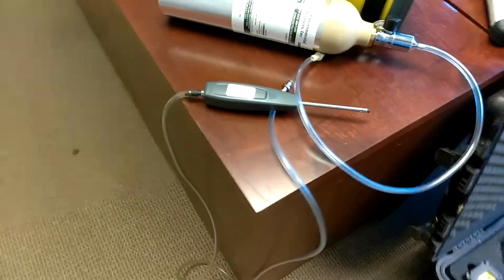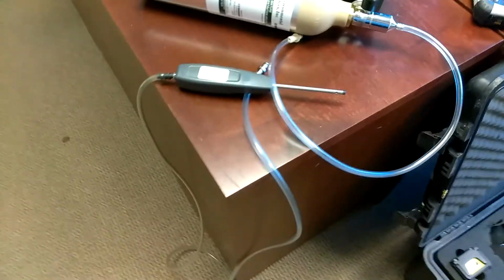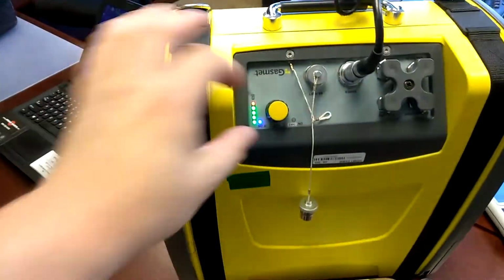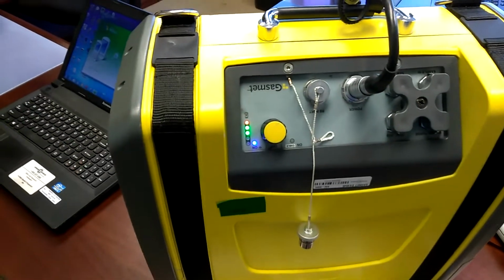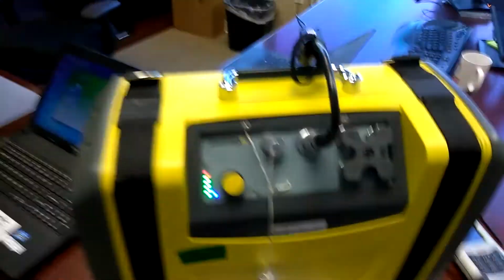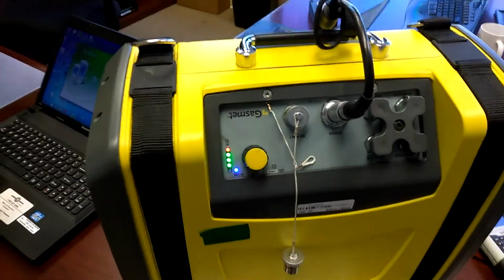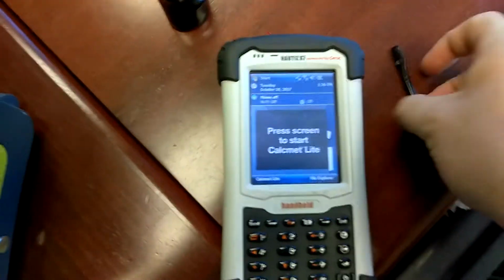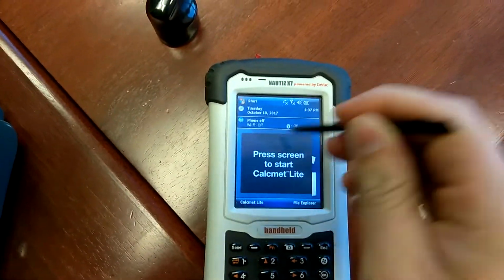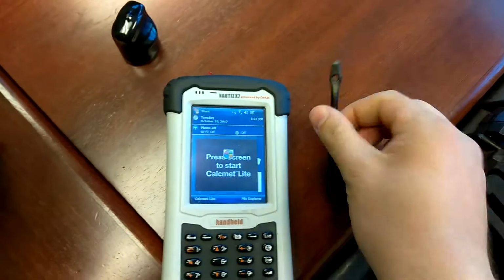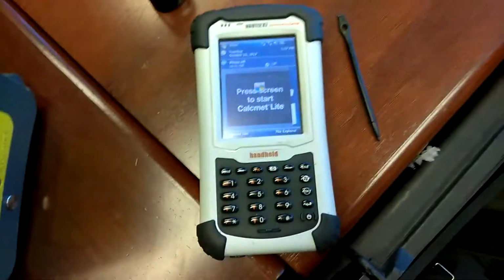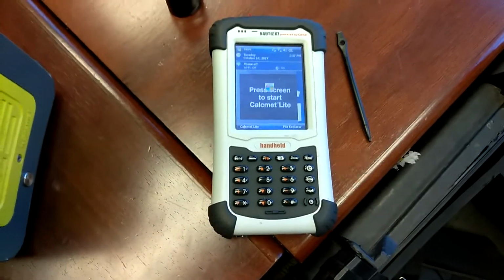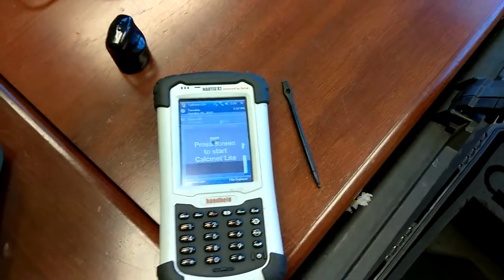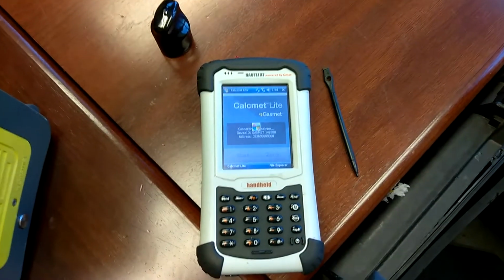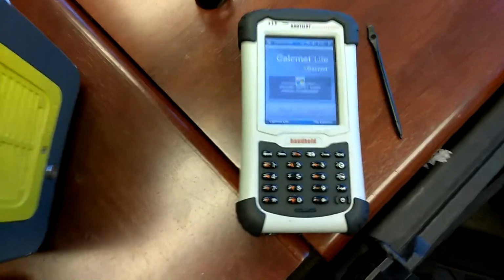We'll also want to have our sampling probe ready, although we won't use it for the zero. Our Gasmet itself is in Bluetooth mode on the left, so that's ready to go. You don't need the power cable for this, although I recommend that you use it because then you're not burning battery to do the zero. Come over to your PDA and go ahead and start CalcMet Lite. You do need to use a stylus for that. The fingertip doesn't work on this particular brand, so I recommend that you have one. That's a replacement that was sent with the rental. Didn't actually come with one on the PDA.